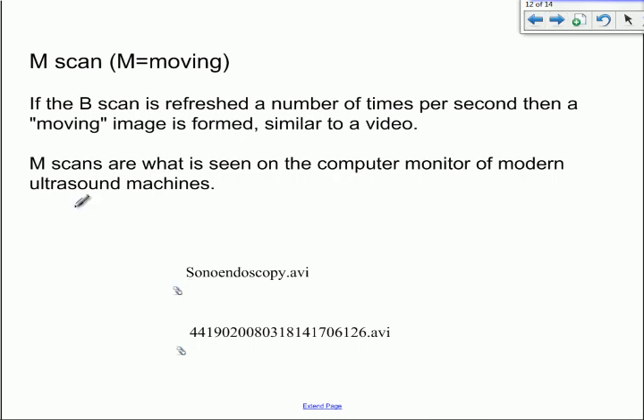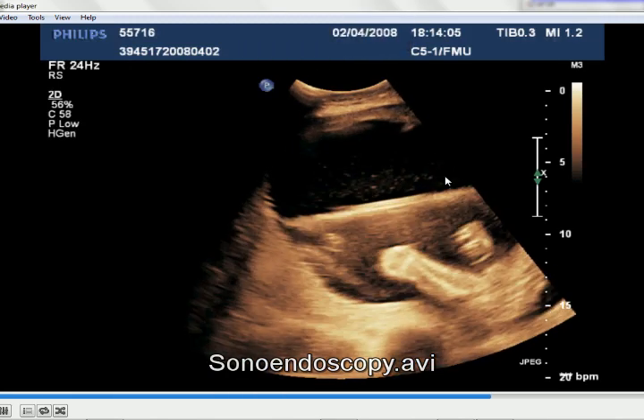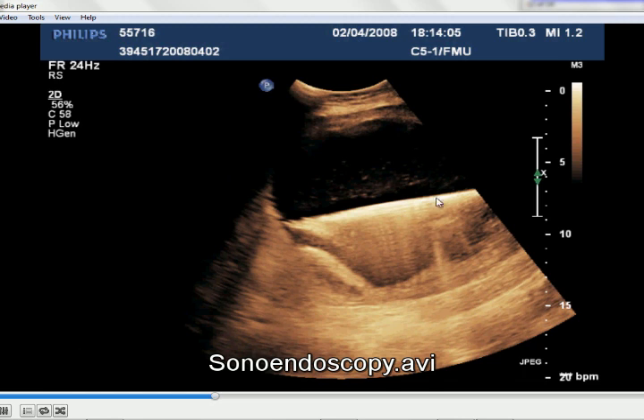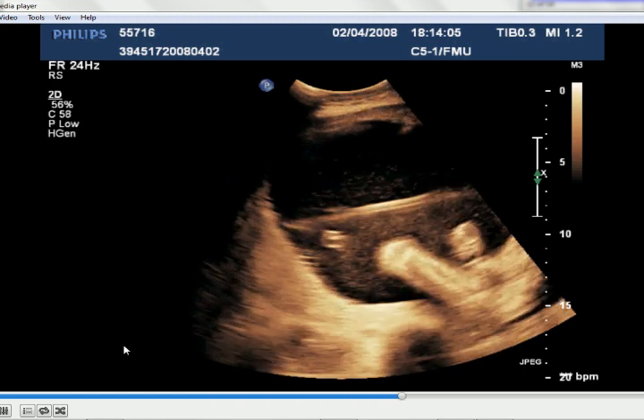And we've got a couple of little videos here. I'm going to show you one of them here, if I can get this to load up. So there we go. So you can see there, each of these individual lines, let's just play that again, each of these individual lines is an A scan. And many A scans at different angles make up a B scan, and that B scan is then refreshed many times a second to give you a moving image. Looks like a fetus's arm there, perhaps.